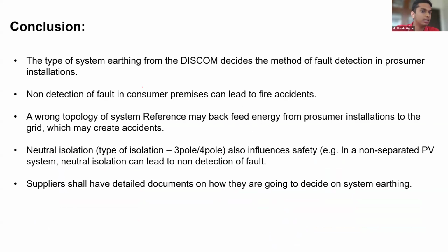Now I'll go to the conclusion. Actually, this prosumer installation subject is a pretty big subject, and I have only tried to simplify it as much as possible. I have only simplified the system referencing conductor on the system. I have not explained how the equipotential bonding and all those things work. Generally, if you follow a normal IS 732 or NEC, all that will be done properly. But the problem is this system referencing changeover will be pretty complicated in prosumer installations.